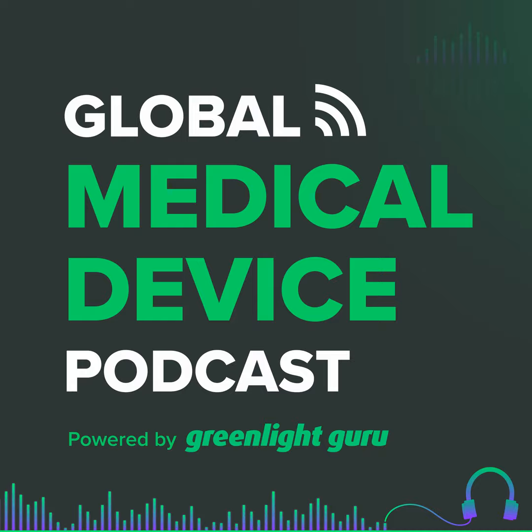It was a class 3 implant device, class 3 United States, 2B in the E.U. Some of these guidance documents, if it's for software, did not apply to us, and N/A goes out of the list. But then some of them were potentially applicable, and they get a little closer look. And if they are directly applicable and can impact our product or risk assessment, then they get a full, really clause by clause gap analysis.